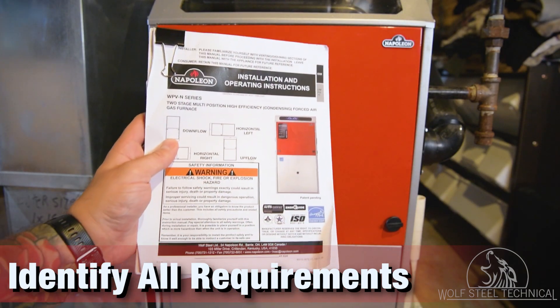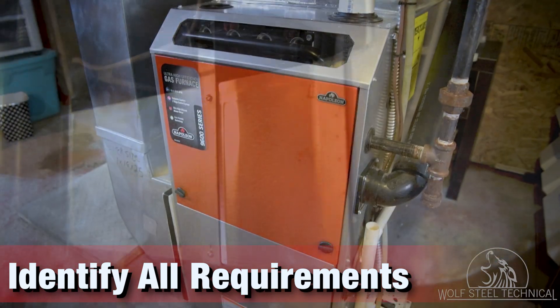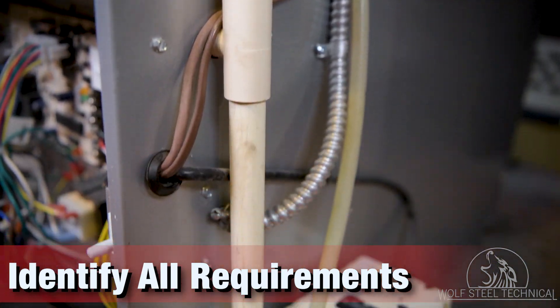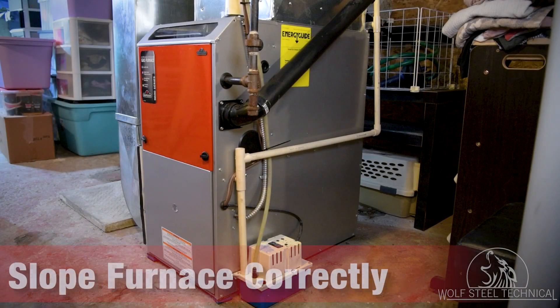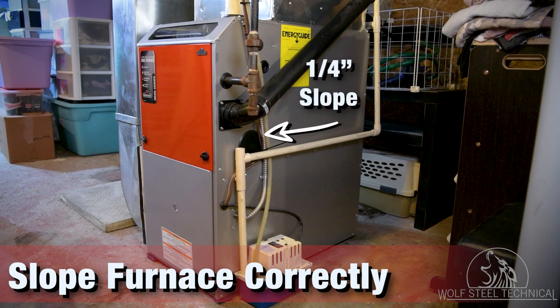When installing any furnace, use the product manual to identify all requirements for venting, supply air, ductwork, service access, clearances to combustibles, and condensate drainage before selecting the final location. Once the final location has been selected, it's recommended that the furnace have a 1/4 inch slope, from back to front, to assist with condensate drainage.